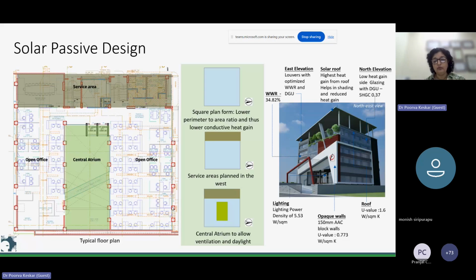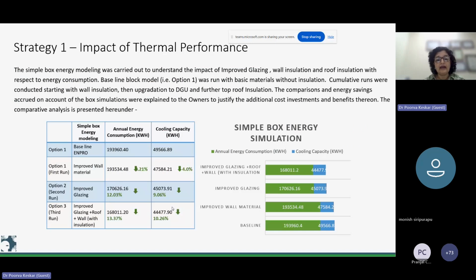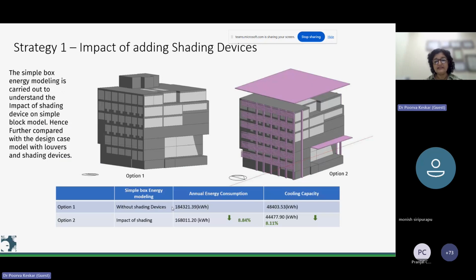So in a simple square form, you start putting in the service areas as buffer zones on the west. By doing simple box energy simulations, we realized that the cooling capacity could be reduced by almost 10.26% by way of improved glazing as well as roof insulation. Now in Pune, I don't think there is any building which has gone in for insulation in the walls. Here we were trying to promote that, but unfortunately the owner didn't really see a lot of benefit in that because we are also working with low energy cooling systems. And at times we were also going to use natural ventilation in certain areas whenever the climate permitted. Here we found that the impact of shading devices could reduce the annual energy consumption by 8.84% and the cooling capacity by 8.11%.